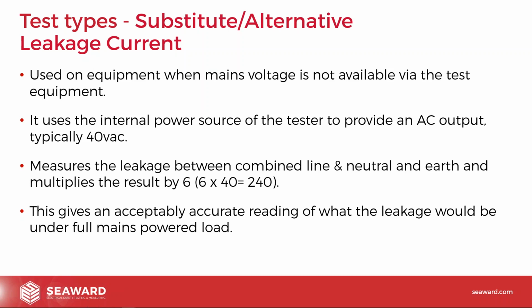We apply this using the battery powered testers, and it gives us an alternative to the other tests where we can't perform them or where they can't be carried out. So the options that we've got for checking the insulation are a 500 volt insulation resistance test, 500 volts DC, a 250 volt test. We can do a protective conductor current test, we can do a touch current test, or we can do a substitute or alternative leakage test.